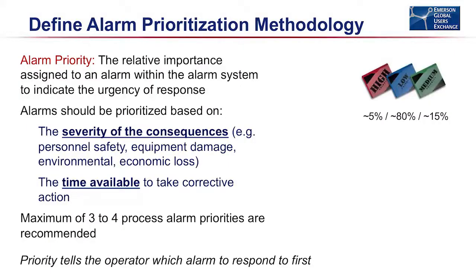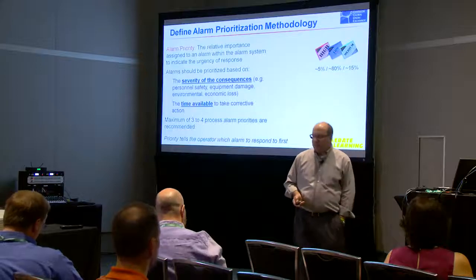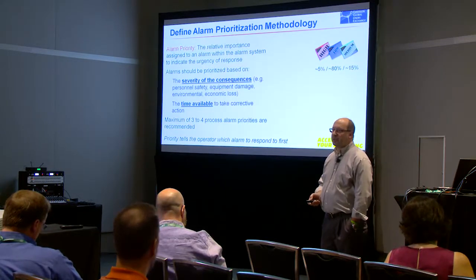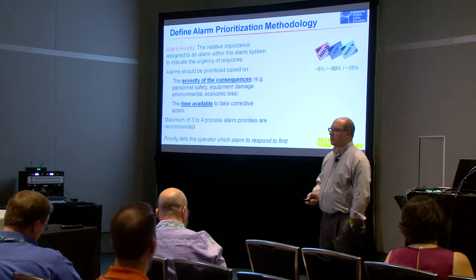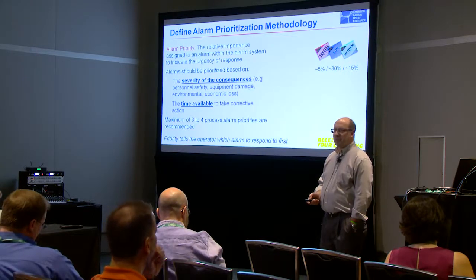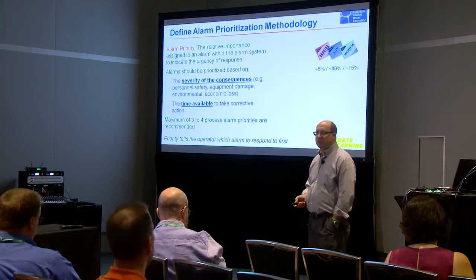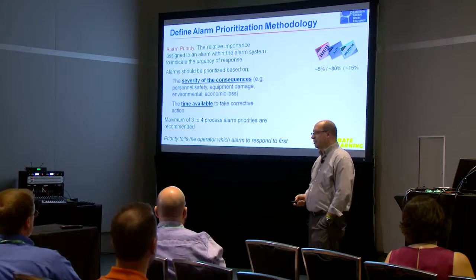Next thing you want to do in your philosophy is define how you're going to prioritize alarms. So what is alarm priority for? That's really the means for the operator to determine which alarm is most important. So if they have two alarms present at the same time, which one do they respond to first? That's what priority is supposed to indicate.